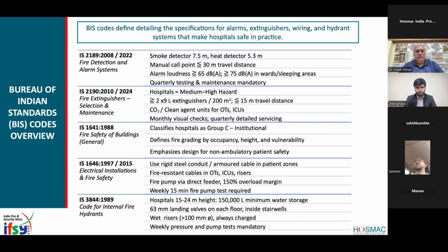The wet riser means it has to be always charged. The pump has to be always in operation. And there is a jockey pump which keeps on hunting. Whenever the pressure drops, like suppose any leakage happens, the jockey pump will automatically start to maintain the pressure of 7.5 kg in the fire water system.